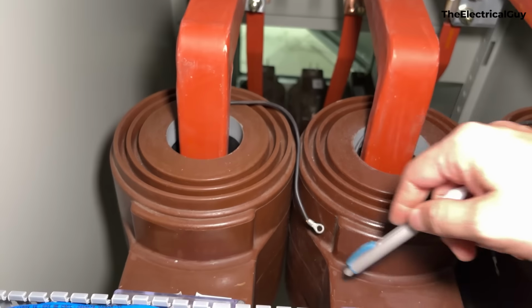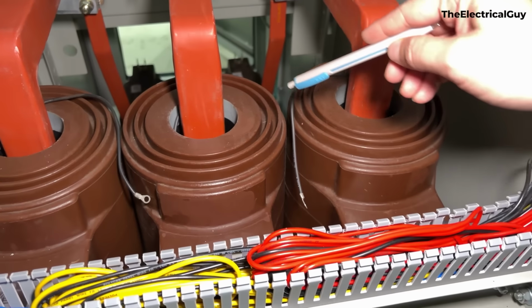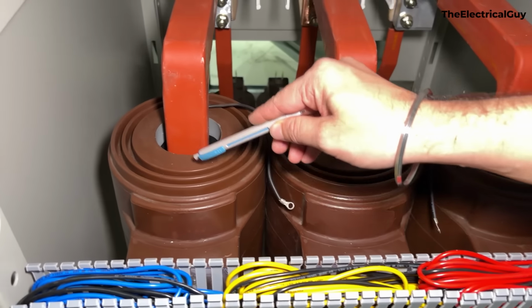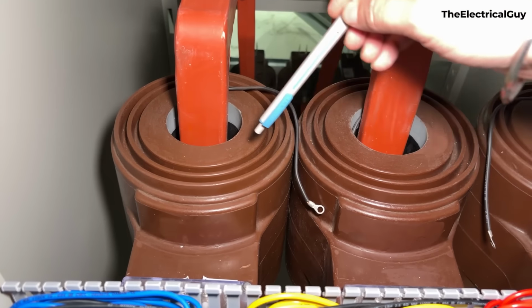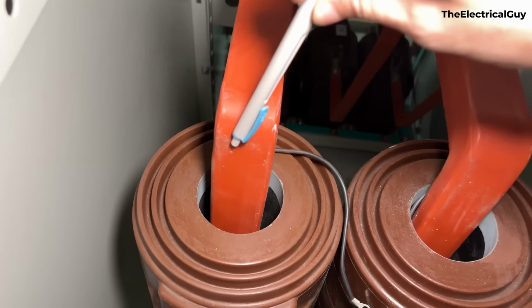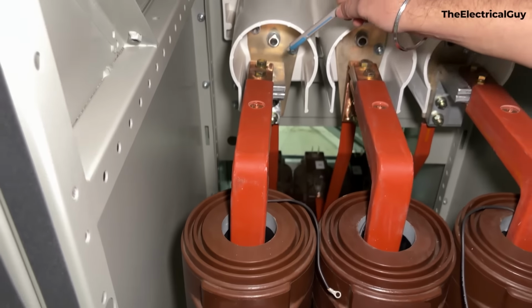So here this is the current transformer that we have. This is R phase, this is Y phase, and this is B phase. So this is a window type current transformer. You can see the bus bar is passing through this and then getting connected to the circuit breaker.